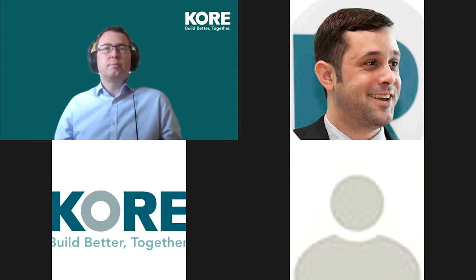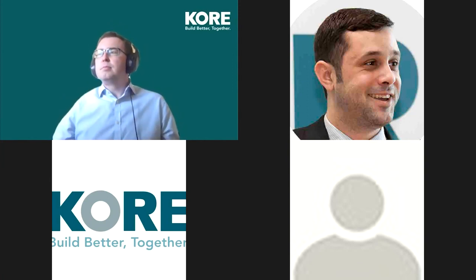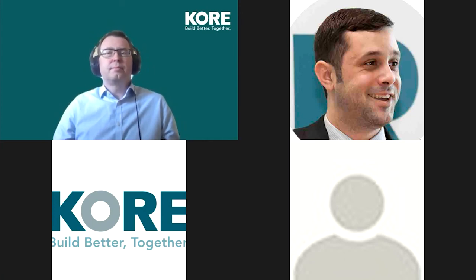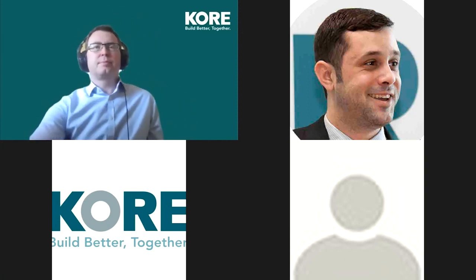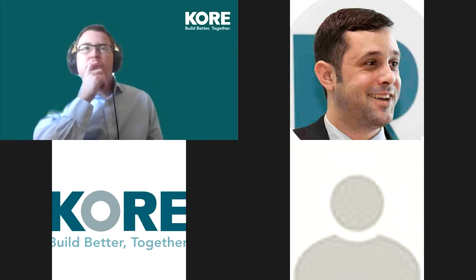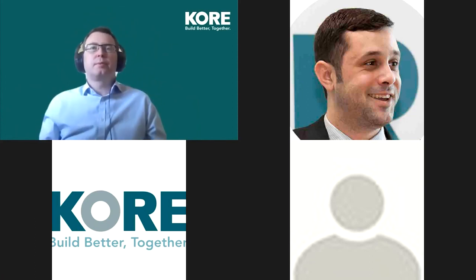Thanks, Andrew. Liam, for a house with 100 mil cavity insulation and 2 inches on internal walls, no underfloor, aluminium rads up and downstairs, is it worth installing a heat pump, or should they revert to steel rads? That's a question from Eva. Hi, Eva. Yeah, I'd imagine you're probably looking at a retrofit if you only have a 100 mil cavity, or do you mean a 150 mil cavity with 100 mil insulation? Either way, and then you have 2 inches on the internal wall. So, yeah, a heat pump will work with aluminium or steel rads. It's just that the rads have to be sized on your heat output. So, what's your duty? What's going into it? What flow temperature are you putting into the rads?